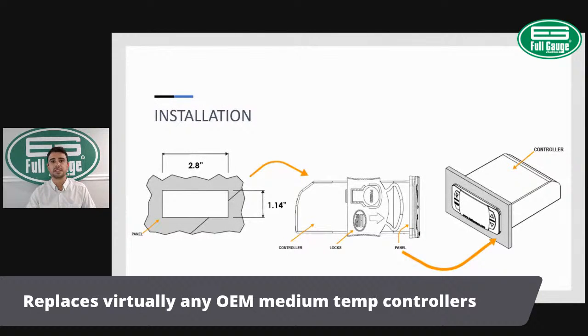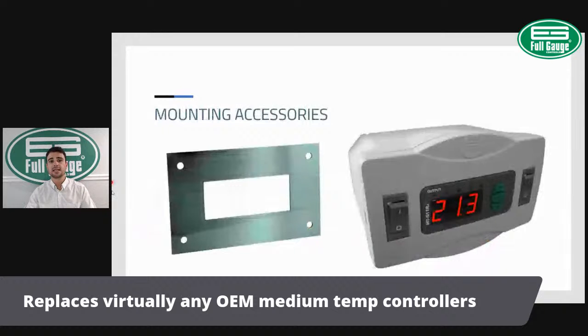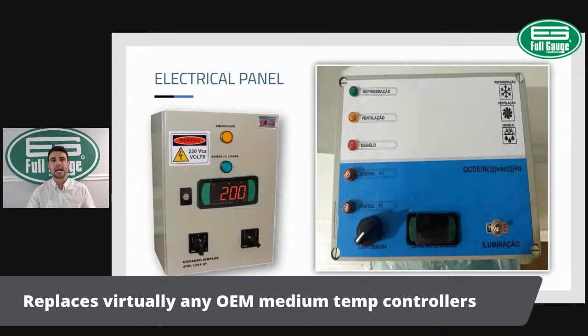We also provide some mounting accessories. We have a mounting plate, a stainless steel mounting plate, and an enclosure. In fact, the enclosure is what I have in here today. I have this enclosure with my MT512 installed on it. Another option for mounting those controllers is in an electrical panel. So a lot of guys like to mount a controller on an electrical panel next to a contactor and a circuit breaker for walk-in applications. That's normally what I've seen, walk-in applications they mount on the electrical panel.